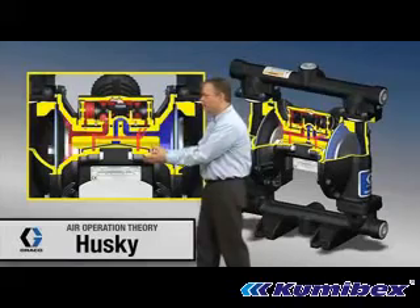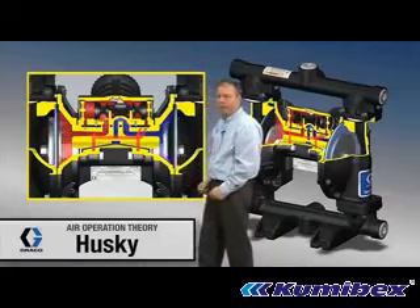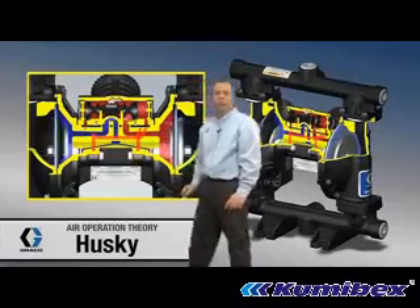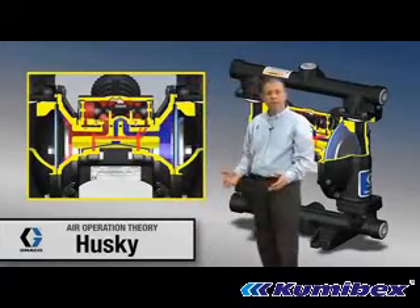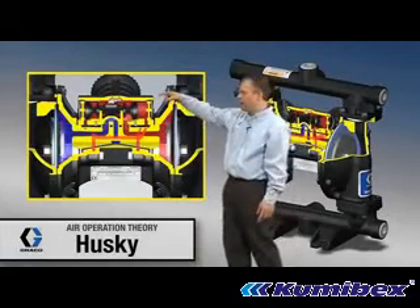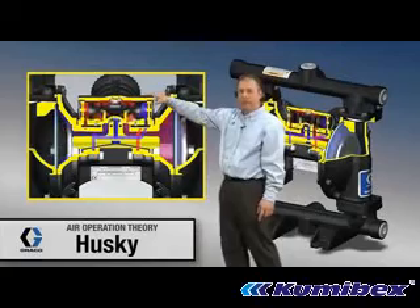Down here, behind this first diaphragm, there's a poppet valve. Over on the other side, another poppet valve. All those pop-it valves do is act as a momentary open air switch, used to dump air pressure on one side or the other of this valve up here.